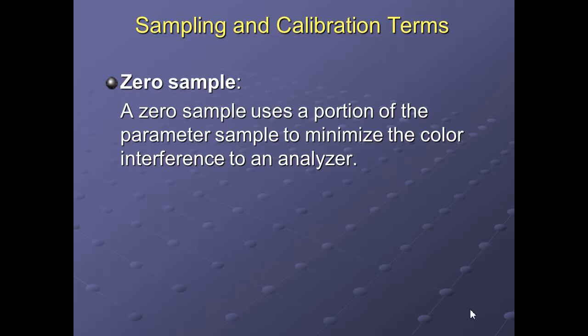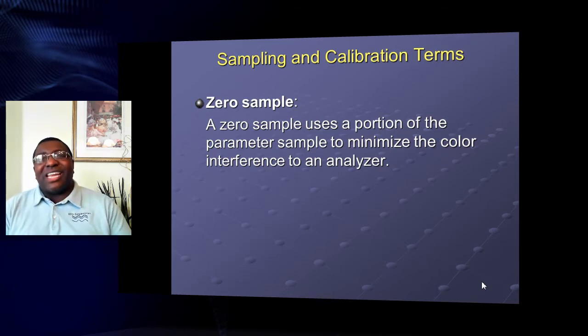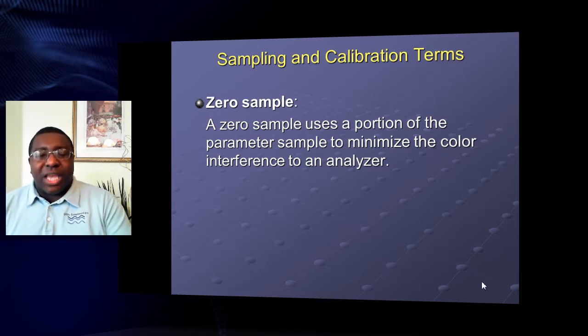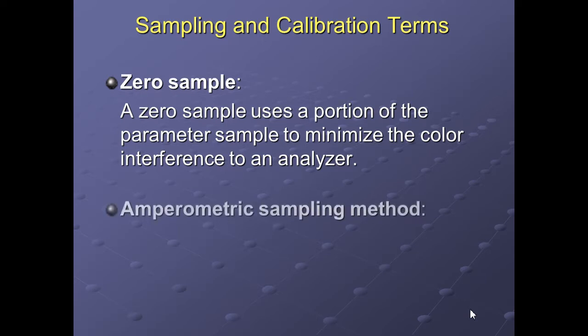The zero sample is different from the blank — the zero sample is a portion of the actual sample. You put it into a vial and tell the machine this is the natural color or natural state of this water before you add any indicating solution, buffer, or reagent. First you have your blank sample to give a baseline, then the zero sample adjusts for the natural field water quality — that color, that TSS of the sample.